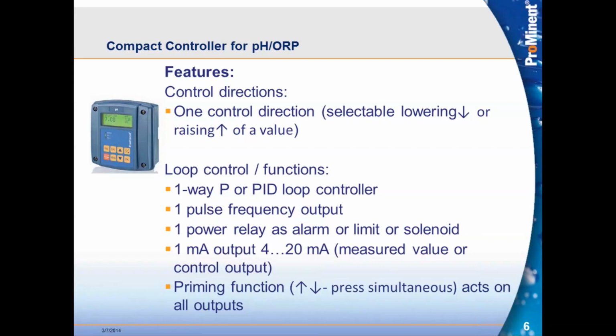As I mentioned, it does offer proportional as well as full PID controller in this very inexpensive package. One pulsing frequency output, you can use that to control your pump. One power relay output as alarm or limit or solenoid actuation. So you can select how you're going to program that unit. We have some selections on that power relay to use it as a limit or to power a solenoid. We offer a milliamp output on this unit. It can be programmed to be either a measured value or a control output. If you don't know the difference on that, please let someone at Prominent know. Talk to your regional manager, and we can definitely help you figure that out.